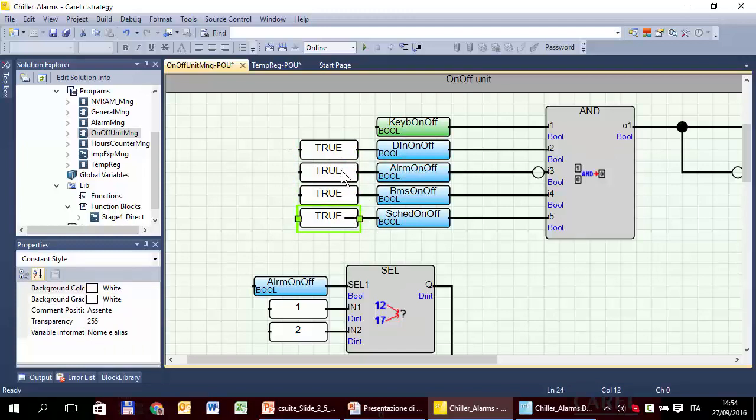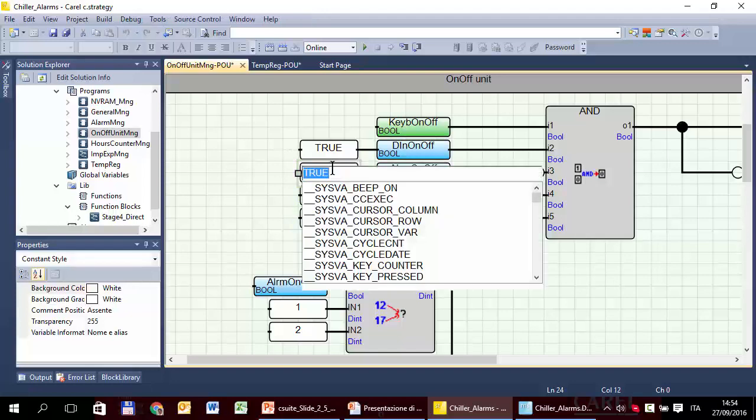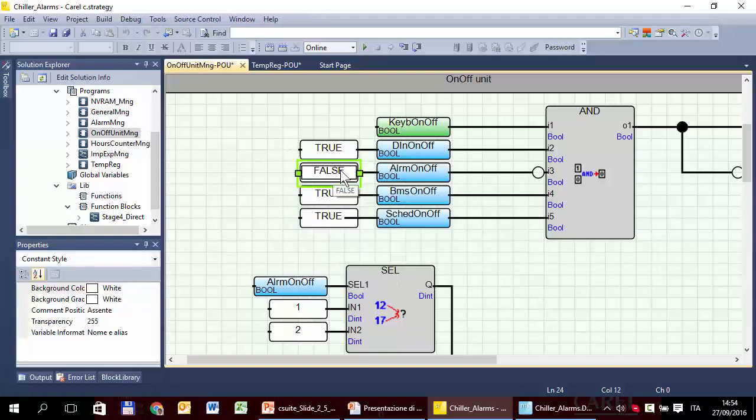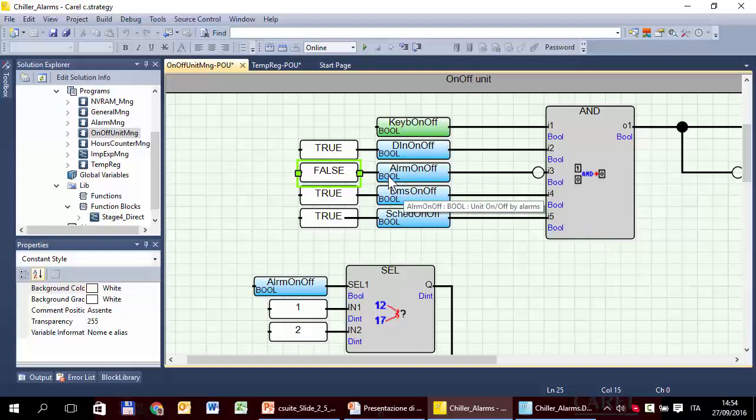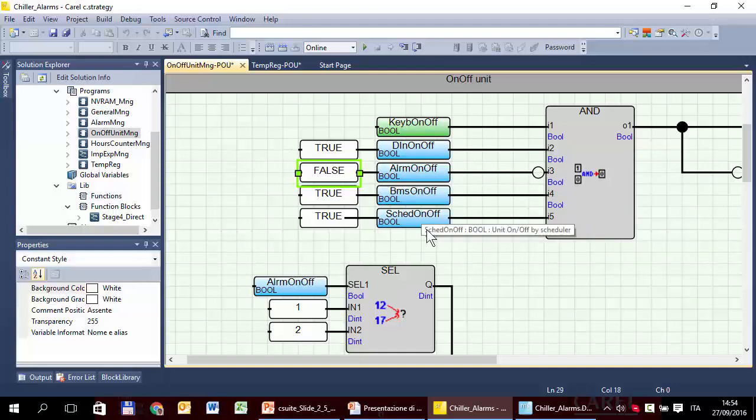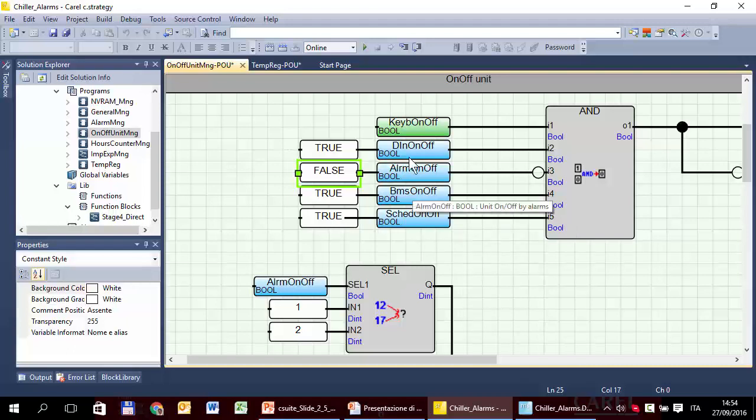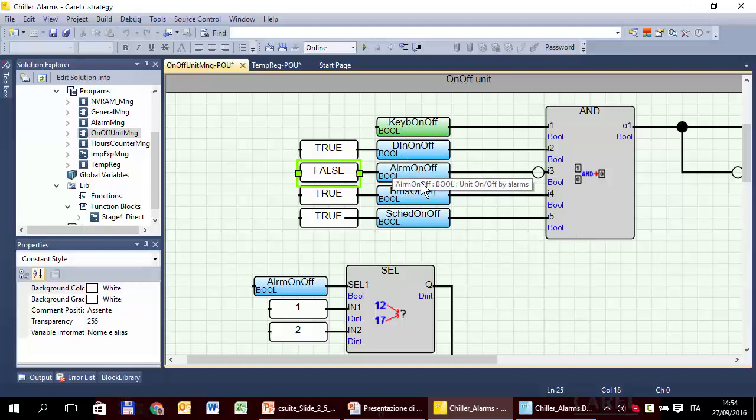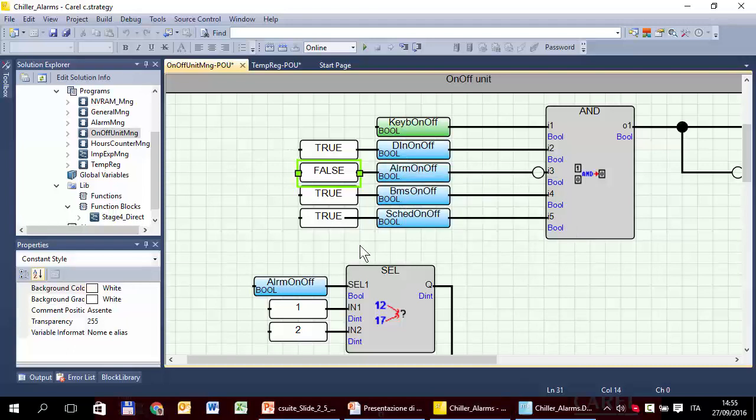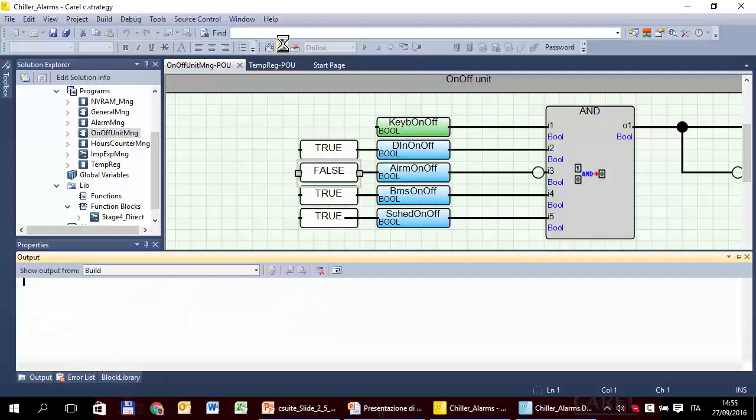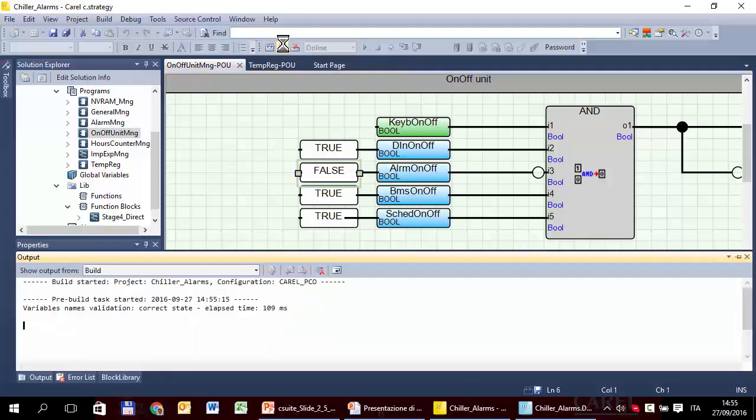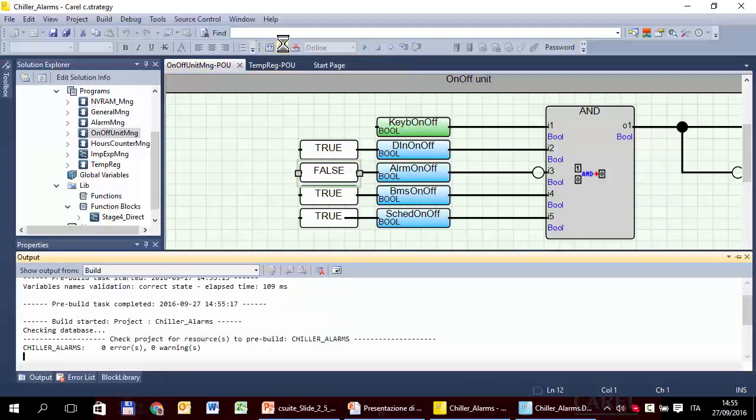We have to change this, because since here there is the not, we have to force to false. False, this is false, not, becomes true, and so on. So, these four variables are forced to a value that corresponds to the unit that can start by digital input, by alarm, by BMS, and so on. Now we can build and check if there are other errors. I don't expect other errors.